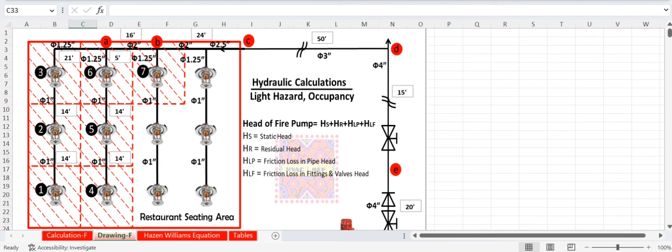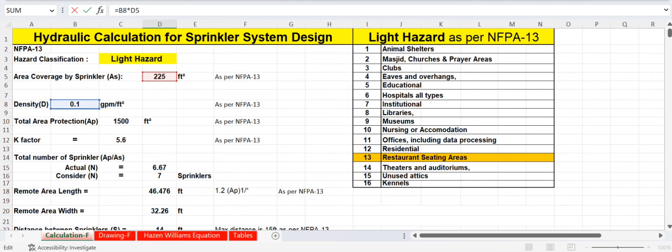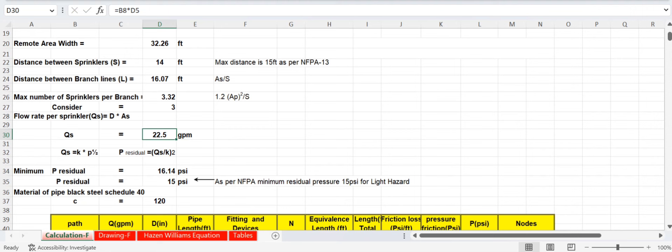Qs is the flow discharged from one sprinkler. The formula is: Qs = density × area coverage = 0.1 gpm/sq ft × 225 sq ft = 22.5 gpm. The square feet units cancel, giving 22.5 gallons per minute from each sprinkler.